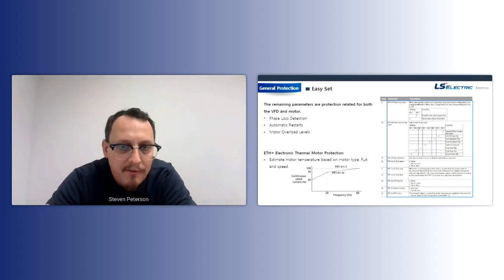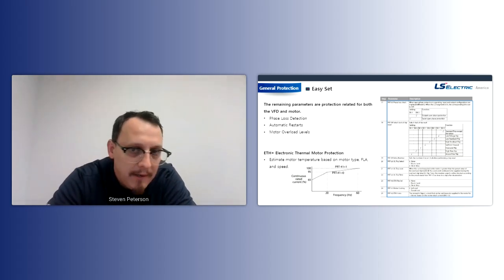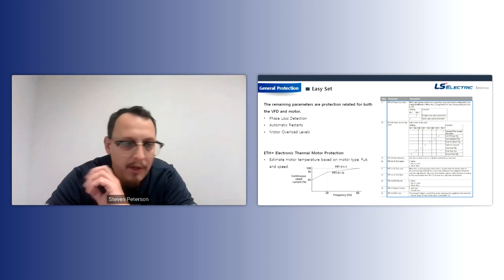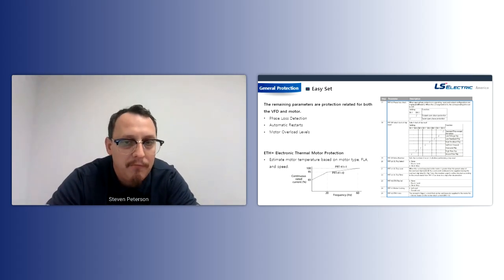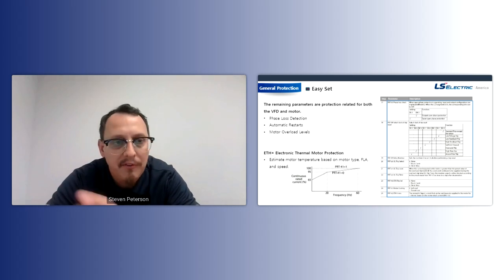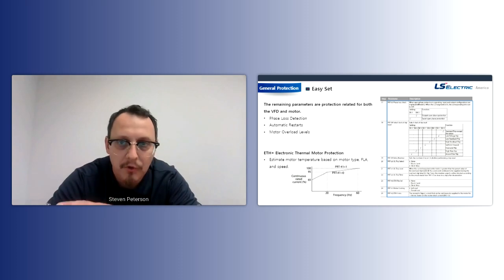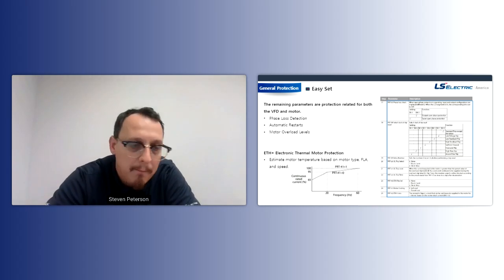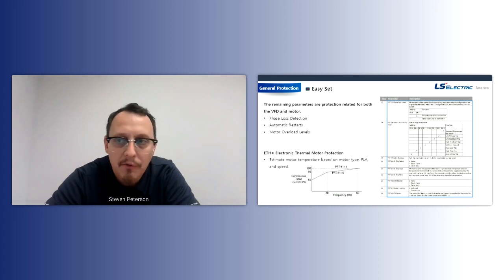So the top one here is phase loss detection. And we do recommend enabling this. Out of the box, they're disabled. So you could apply this for single phase and you could run it without a motor and the drive will be fine. But whenever you're ready to finish commissioning this and put it in auto mode and run it, we'd recommend having these two bits up. The bit on the left for this parameter is input phase loss detection. So if you ever go from three phase to single phase by mistake and you clear a fuse or a wire comes off, the drive's going to detect that. It's going to trip out to protect itself. And then the other bit is for pretty much motor protection. If a wire falls off or there's some issue in the motor, the drive's going to detect that and say there's a phase loss issue. Okay, so it's going to stop operation.